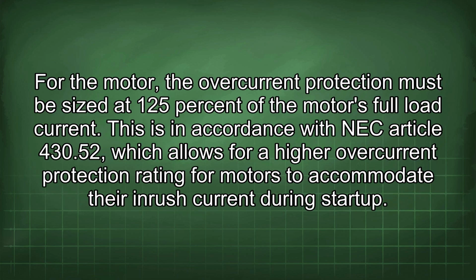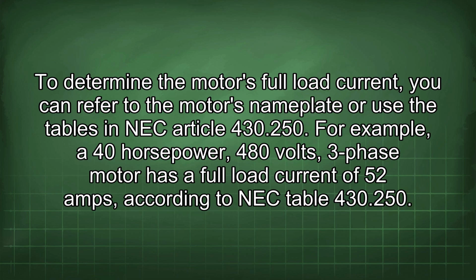For the motor, the overcurrent protection must be sized at 125% of the motor's full load current. This is in accordance with NEC Article 430.52, which allows for a higher overcurrent protection rating for motors to accommodate their inrush current during startup.